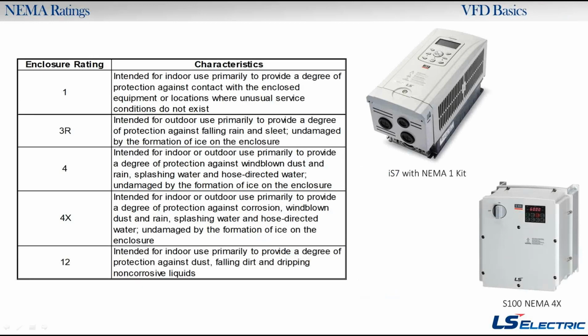So I just have a few more things here, which is enclosure ratings. There's a million enclosure ratings, but mostly what we care about in the US is the NEMA ratings, and within those, these are some of the more common ones. There's NEMA Type 1, which is the first one. This is meant for indoor. It's going to have a certain degree of protection against contact. If you look at that IS7 with the NEMA 1 kit, also commonly called a conduit kit, it's kind of a finger-proof design, okay? So you can't get your finger in there, you can't get zapped unless you really try hard.